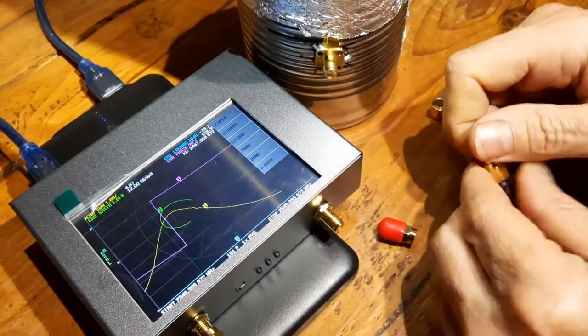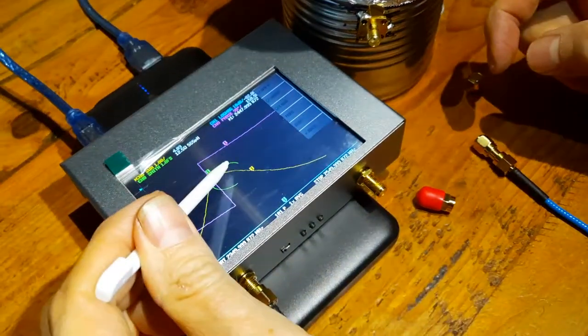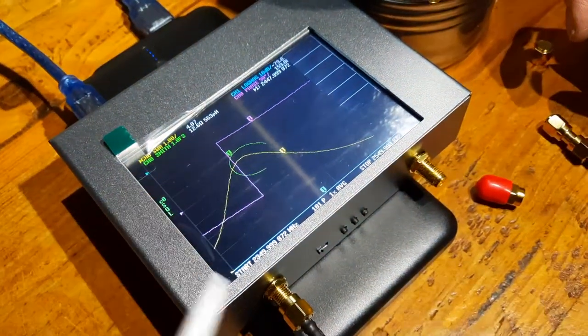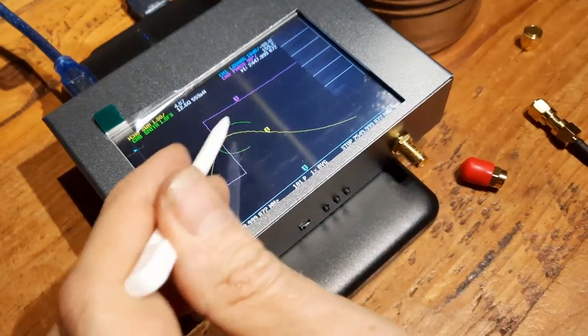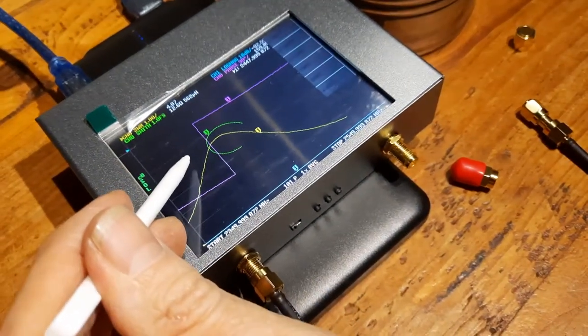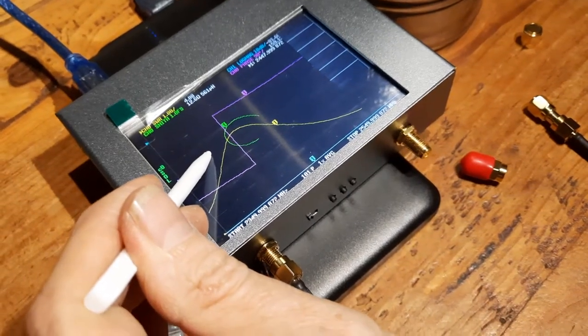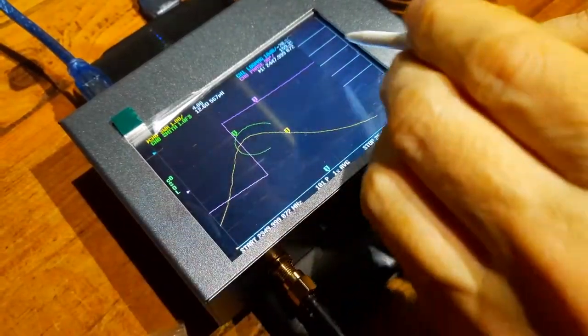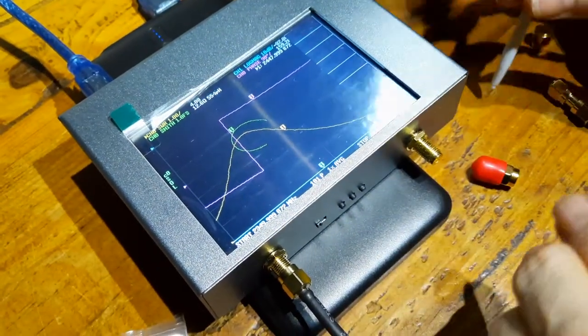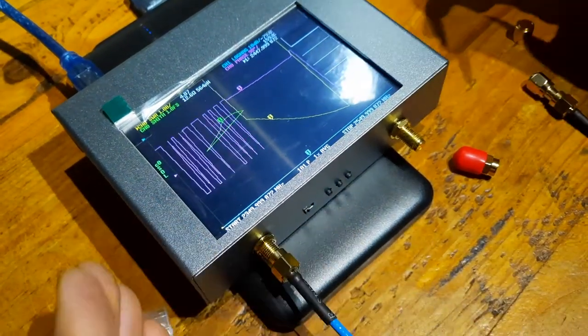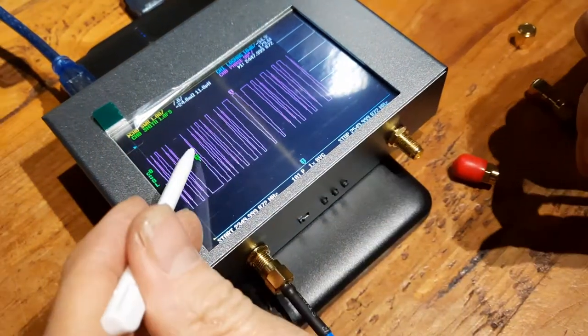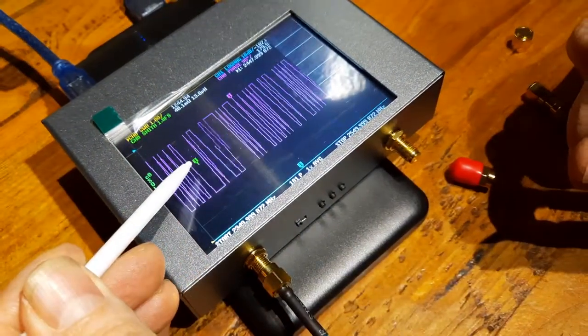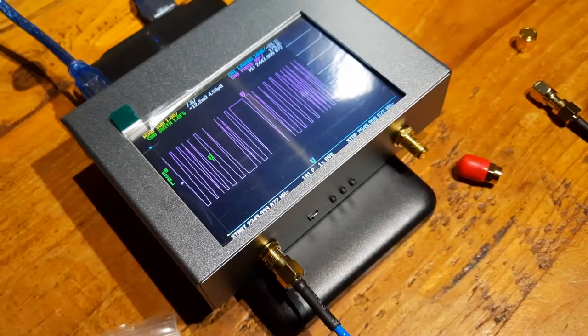You can see the green line here is not quite, the green line is the main thing you need to focus on on the Smith chart here. But that should be like right here and it shouldn't have an arc. So now when I hit short, okay now you see that it put the thing right on exactly where it's supposed to be.